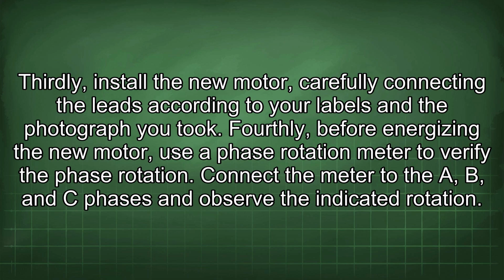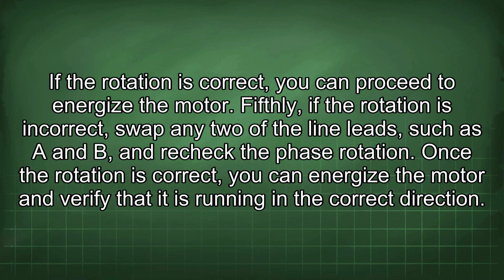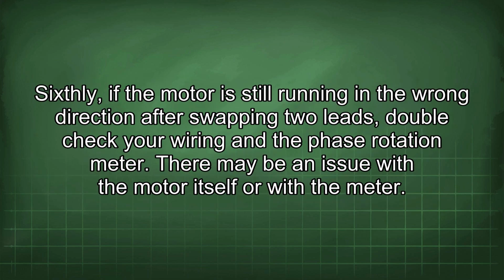Fourthly, before energizing the new motor, use a phase rotation meter to verify the phase rotation. Connect the meter to the A, B, and C phases and observe the indicated rotation. If the rotation is correct, you can proceed to energize the motor. Fifthly, if the rotation is incorrect, swap any two of the line leads, such as A and B, and recheck the phase rotation. Once the rotation is correct, you can energize the motor and verify that it is running in the correct direction. Sixthly, if the motor is still running in the wrong direction after swapping two leads, double-check your wiring and the phase rotation meter. There may be an issue with the motor itself or with the meter.